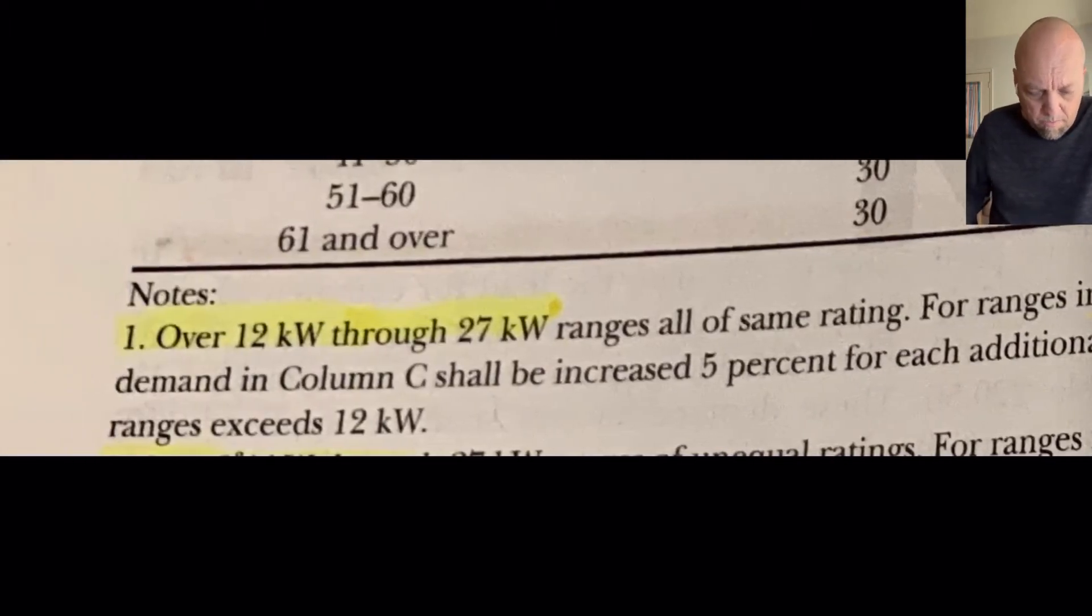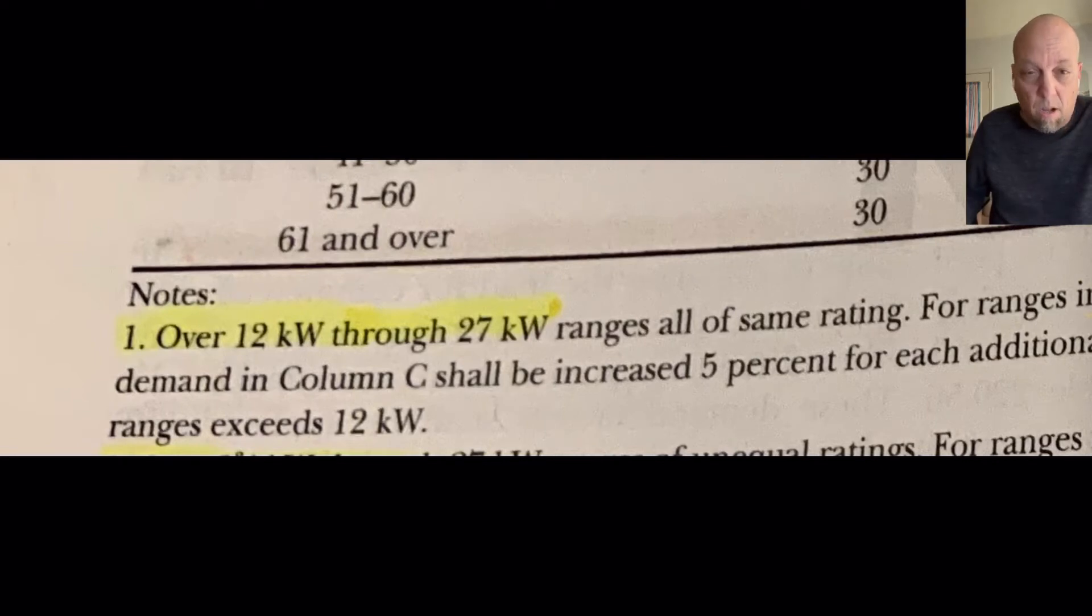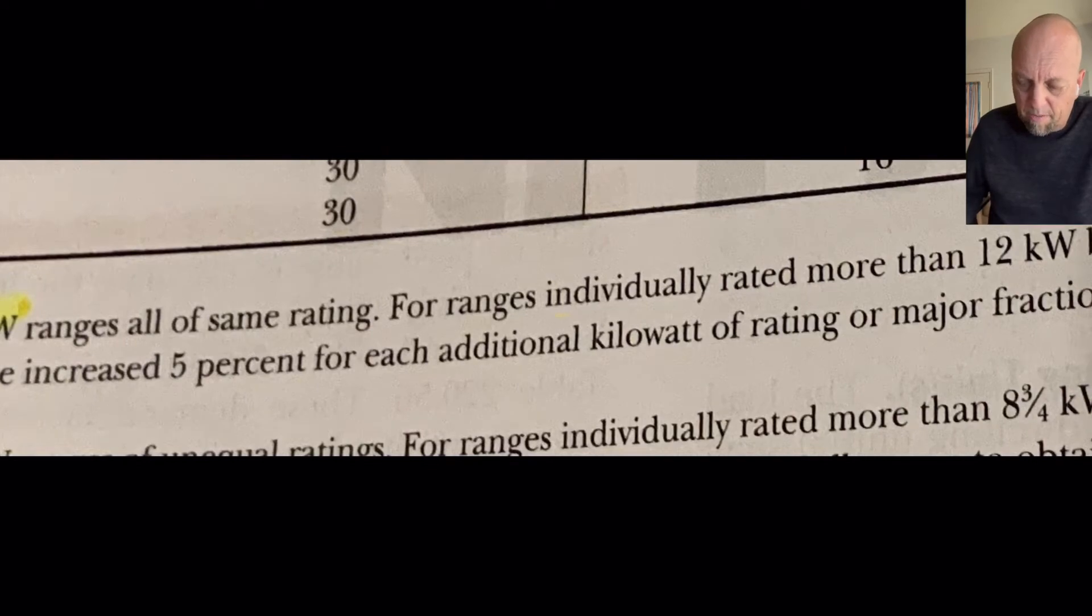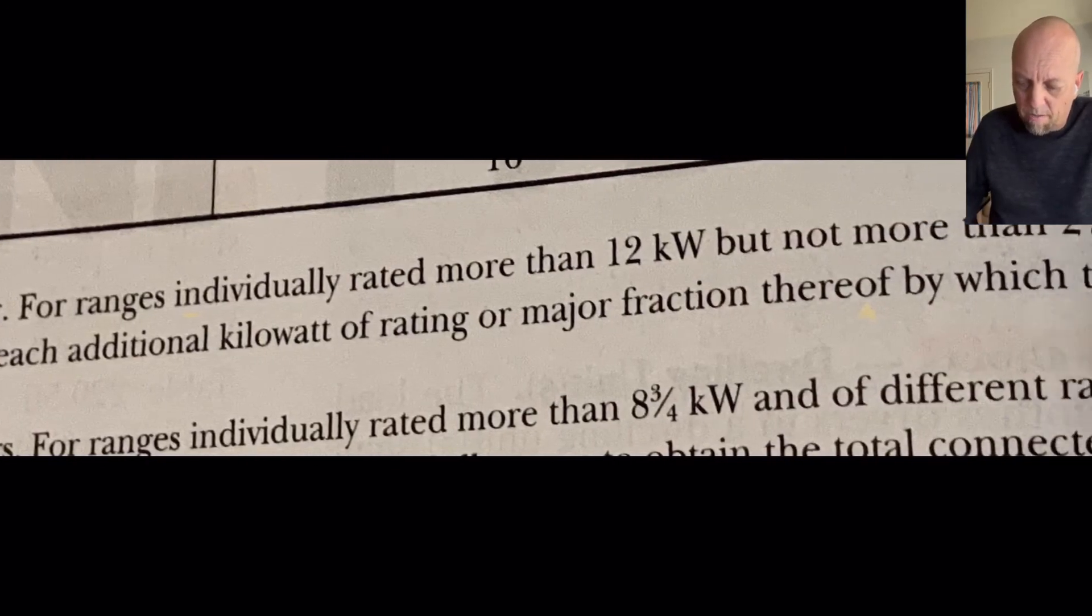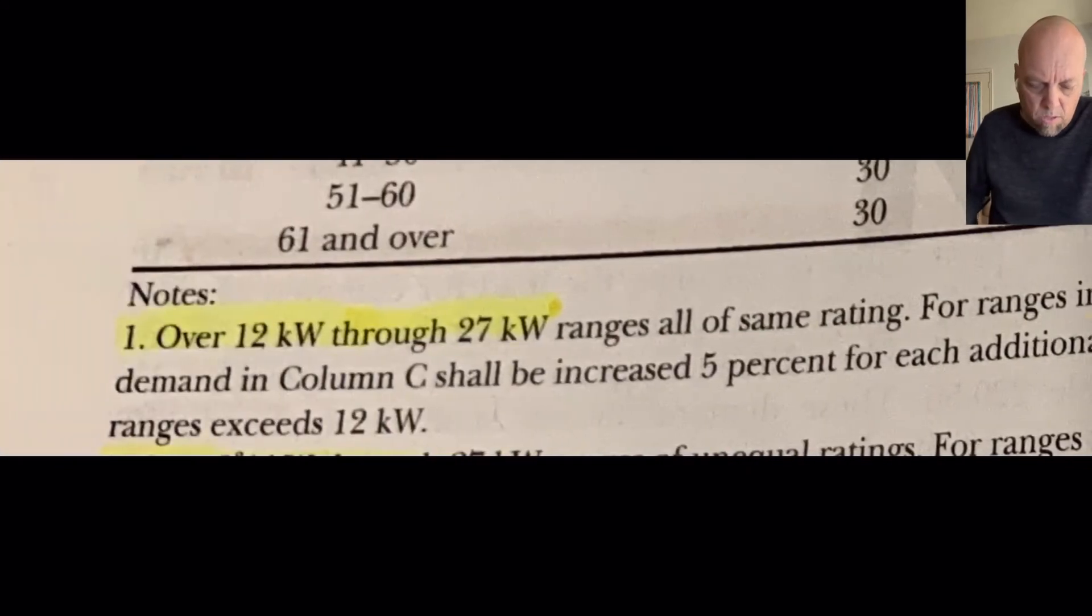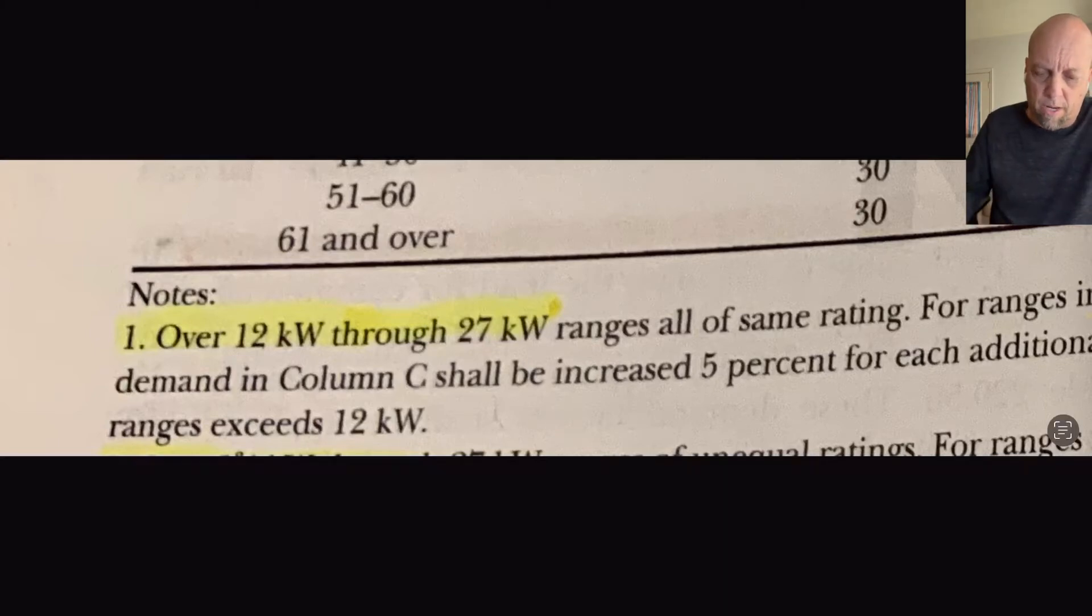the maximum demand in column C shall be increased 5% for each additional kilowatt of rating or major fraction thereof by which the rating of the individual ranges exceed 12kW. So, that being said, 12kW is kind of the thing. 12kW is the limit. After 12kW, you take this note into consideration.